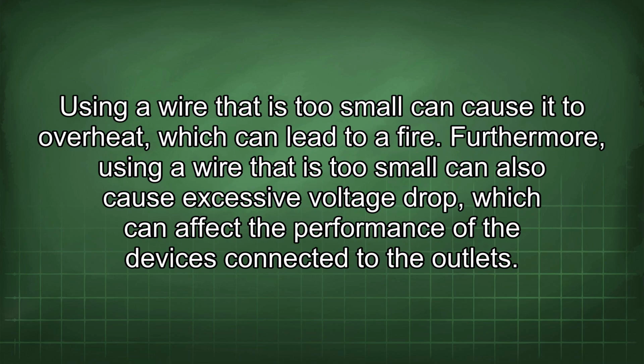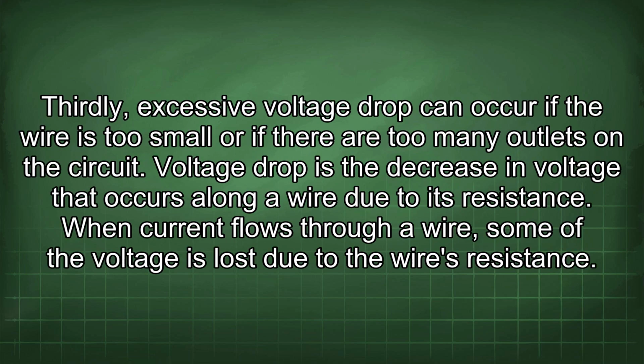Using a wire that is too small can cause it to overheat, which can lead to a fire. Furthermore, using a wire that is too small can also cause excessive voltage drop, which can affect the performance of the devices connected to the outlets. Thirdly, excessive voltage drop can occur if the wire is too small or if there are too many outlets in the circuit. Voltage drop is the decrease in voltage that occurs along a wire due to its resistance.